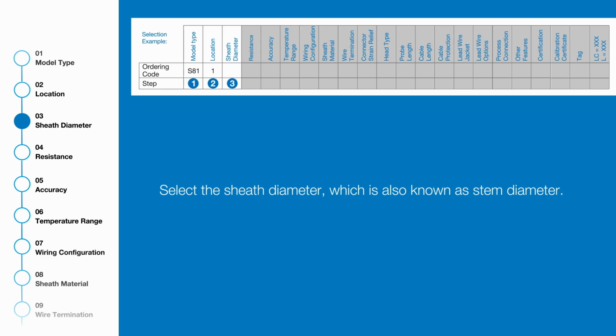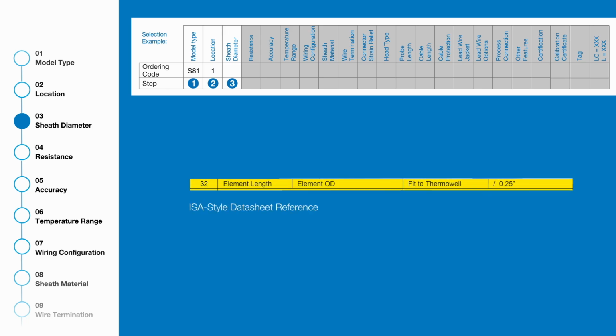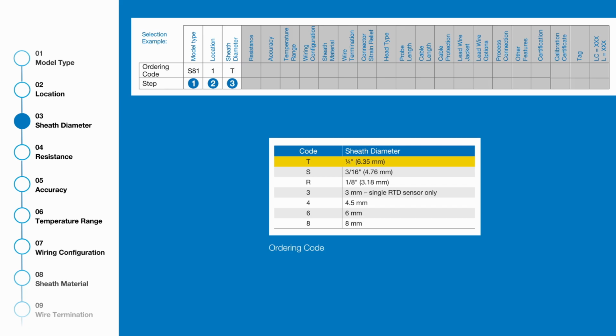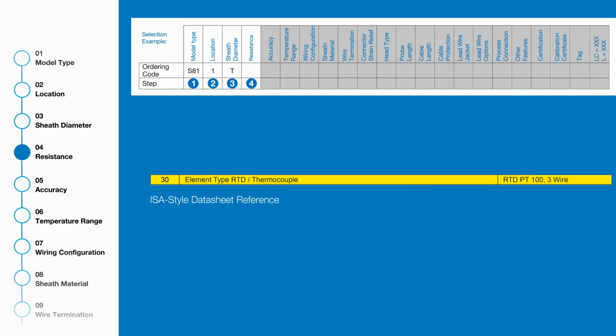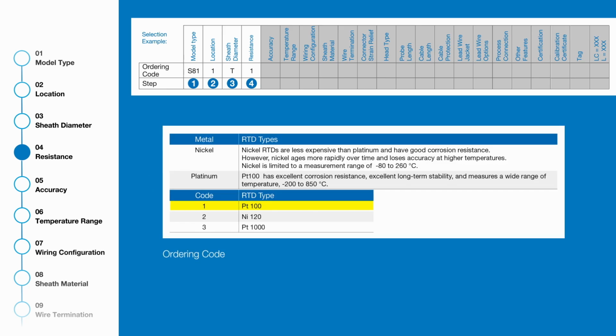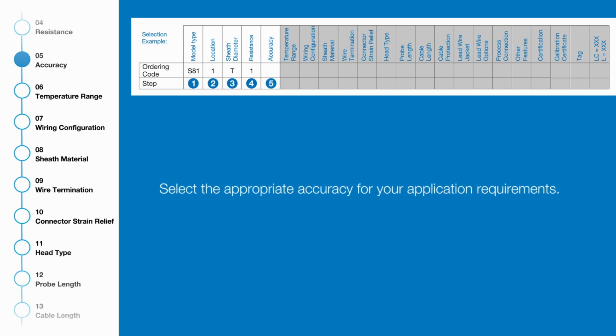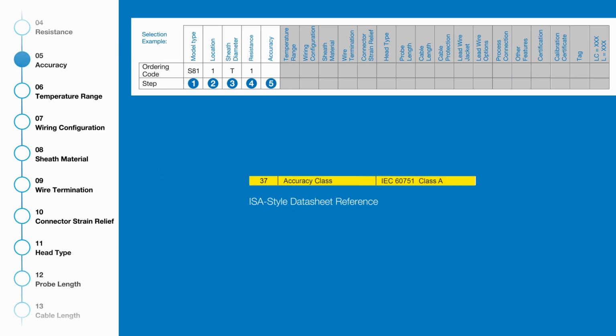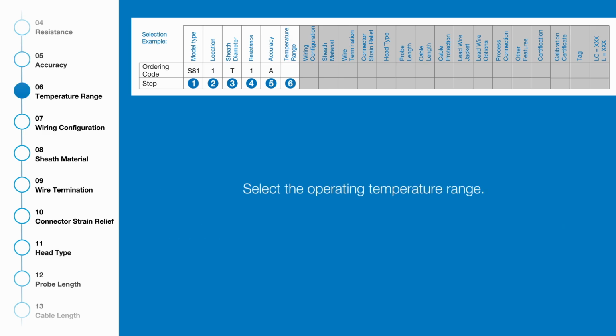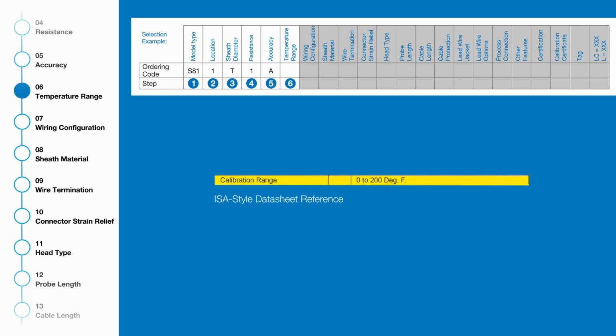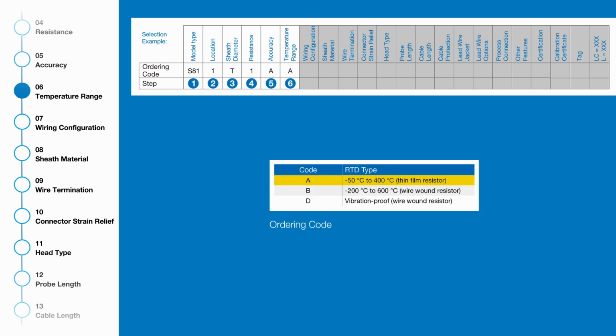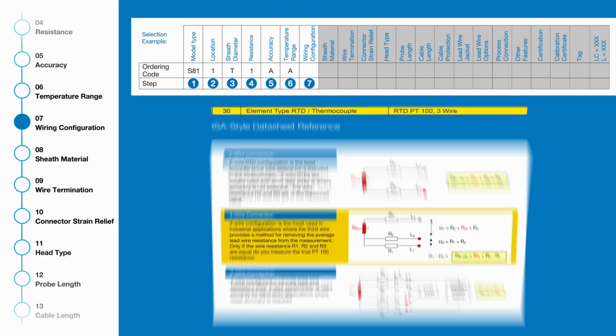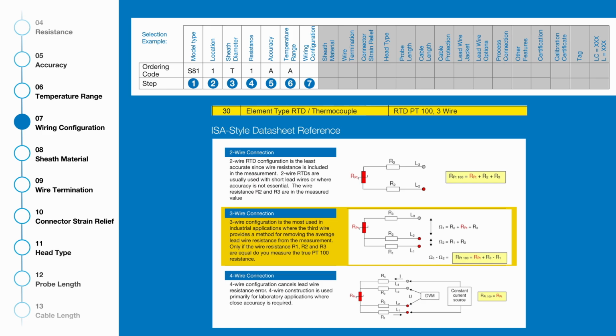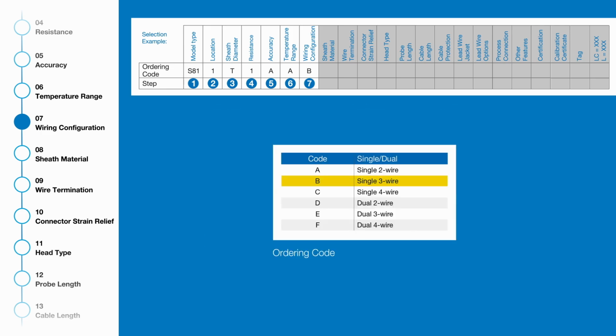For the sheath diameter, the requirement was 1/4 inch. We're going to select code T for 1/4 inch. The RTD resistance, we saw from the requirement, is a PT100, so 100 ohms. So we're going to select code 1 for PT100. The accuracy requirement was class A, so we're going to select code A. The calibration range was 0 to 200F, so we are going to select the code A, thin film RTD. The wiring configuration requirement was for 3-wire, so we're going to select code B for a single 3-wire RTD.